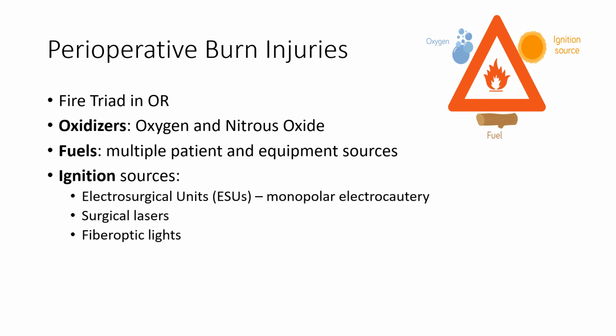Oxidizers are not fuels and are not consumed in a fire, but act to accelerate the burning process. An ignition source, such as heat, is the remaining element in the fire triad. Although it is possible for flames to erupt when an ignition source comes into contact with the fuel and room air, the flame will be more intense and severe in an environment with an increased concentration of oxygen.